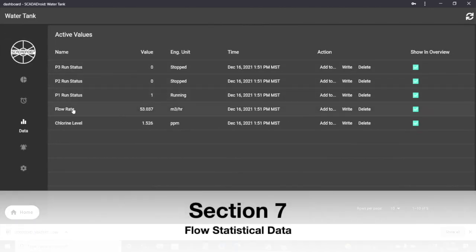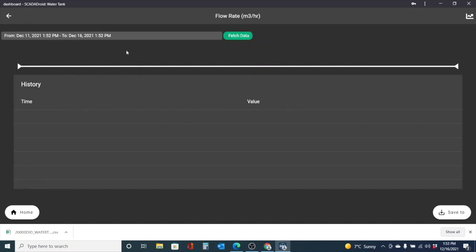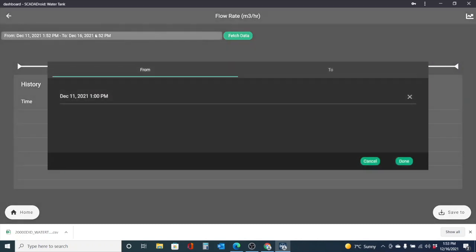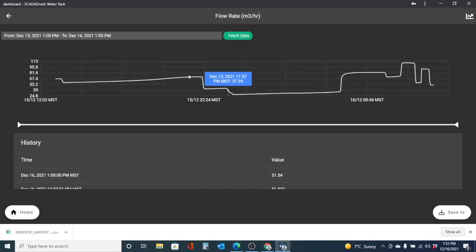Flow rate is a very similar process to the tags such as chlorine, pressures, or levels. After you click the flow rate button, you will be presented with this screen. Whenever the Cloud SCADA recognizes a tag that is a rate, such as a slash meaning per in the units, or a unit measurement such as GPM, it will totalize that tag. The tag on this screen is a flow rate. However, it could also be a kilowatts/hours or any other rate. Note again that the units for the tag are configured in the SCADADroid.